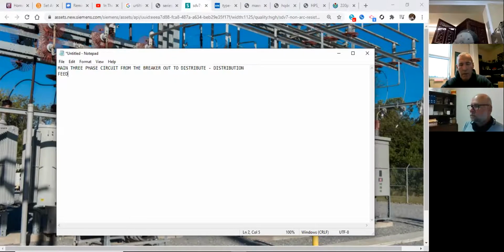Feeder is specifically NOT fused, correct? The only protection that you have on your feeder out there in the world is the breaker itself. So I'm not going to go down a portion of feeder line, put a fuse in it, and then continue on with the feeder line. It's not fused. Its only protection is a breaker.